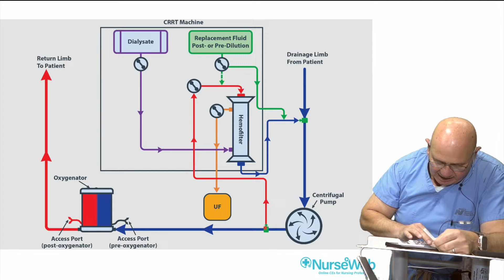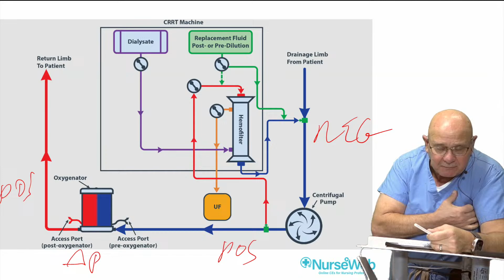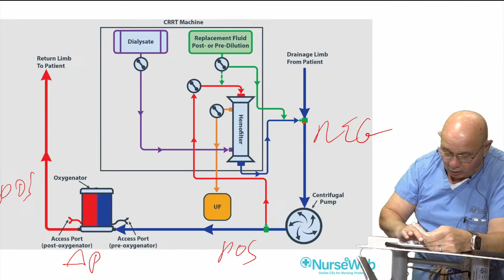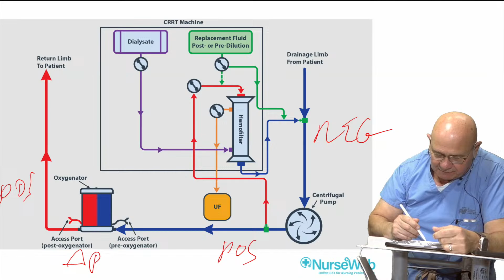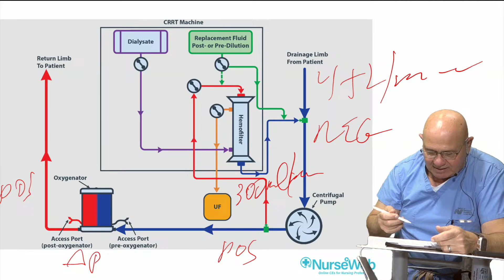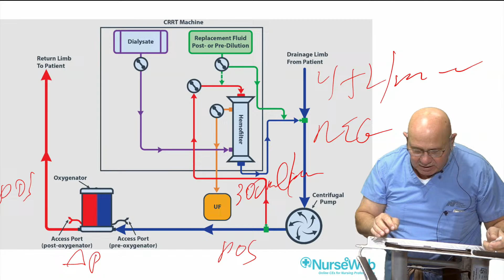We all know this. So here's your blood going out of the circuit, going with a pump, so you're controlling the blood flow, going into the hemoconcentrator, and it's going back in on the negative side. Now, you would imagine that if I have it connected to the negative side, a couple of things are going to happen. One, some of this blood is going to get recaptured, so you're going to have increased recirculation. Exactly. However, because the blood flow is probably 4+ liters per minute, and the blood flow through this is, let's say, 300 mLs per minute, you could see that the amount of recirculation that would occur in that situation is probably going to be negligible at best. So keep that in mind.